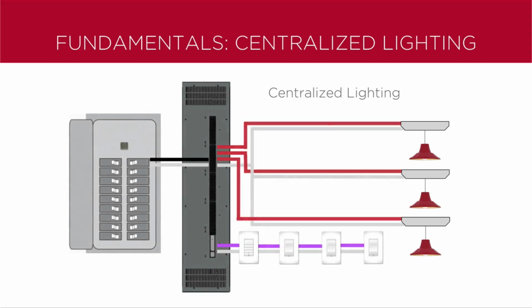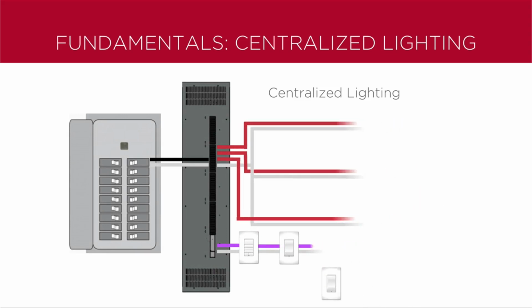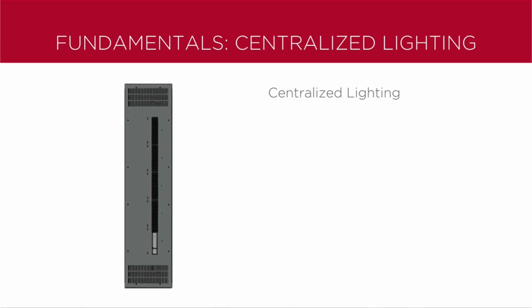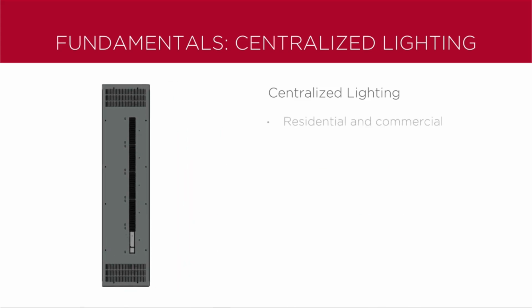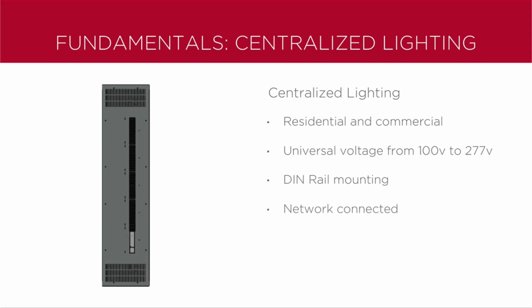Centralized lighting is more robust and reliable and has failover control scenarios. However, it's limited to new construction or major remodels. The Control4 centralized lighting solution can be used for residential and commercial applications, and accepts universal voltage from 100 volts to 277 volts. The modules are mounted using the DIN rail standard and are all network connected, and those centralized lighting loads can be controlled from any interface: a keypad, a touchscreen, the on-screen, or the Control4 apps.